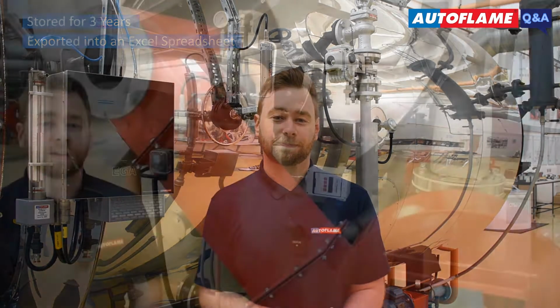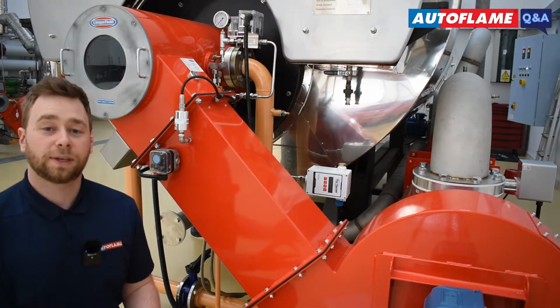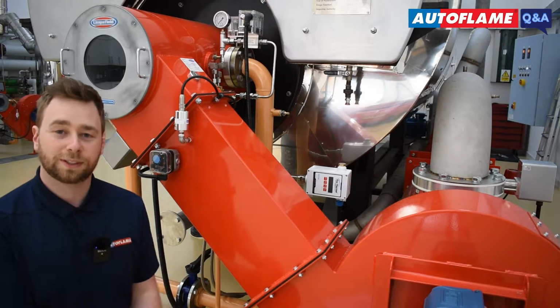Now, all this valuable fuel data can be viewed on the EGA even if no other Autoflame equipment is present on site. This data, along with all of your emissions data, is stored on the EGA for 3 years and can be exported into an Excel spreadsheet for external data logging and emissions reporting. All we will require is a mass flow meter that's capable of outputting a 4 to 20 milliamp signal.